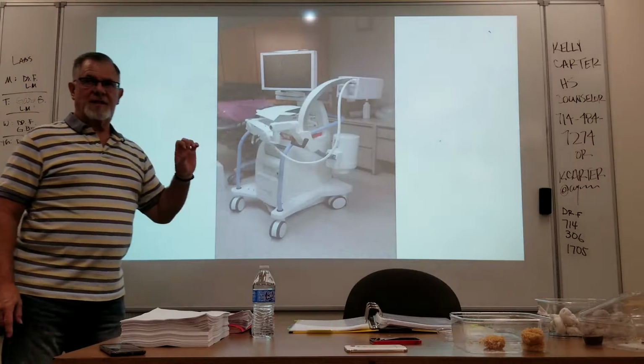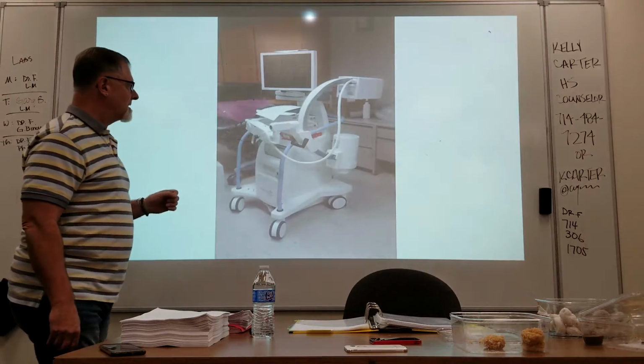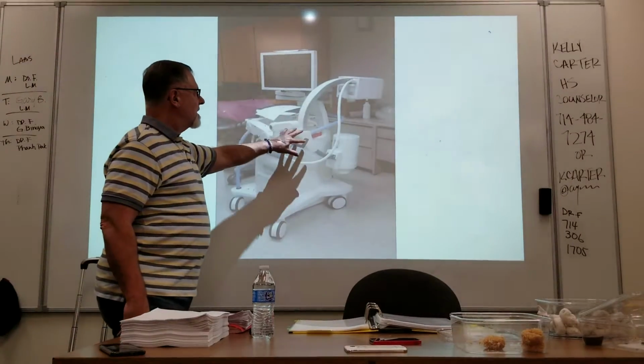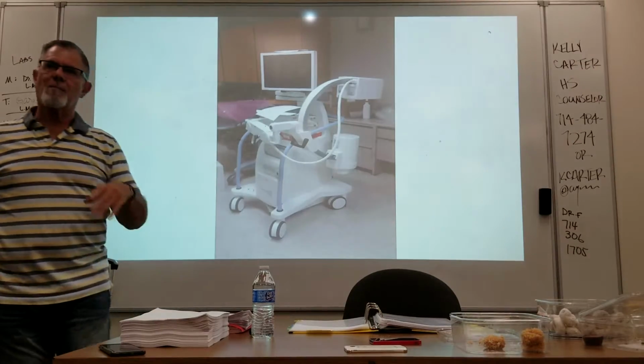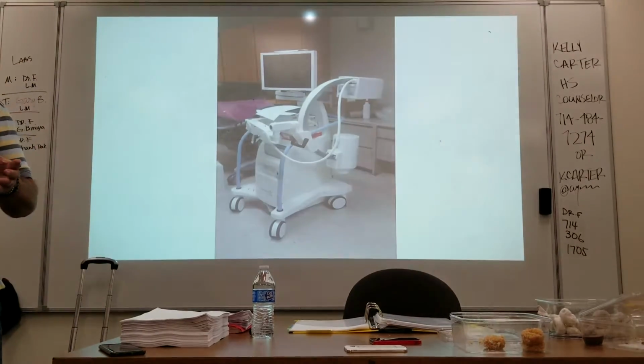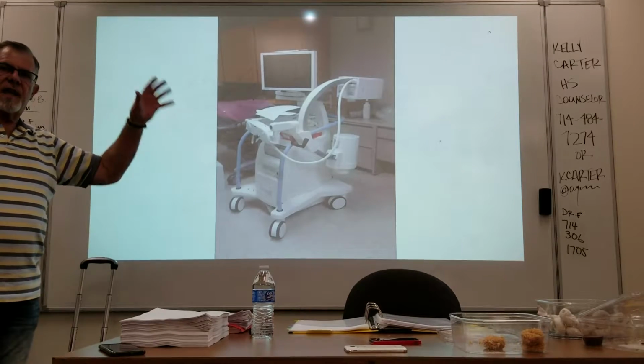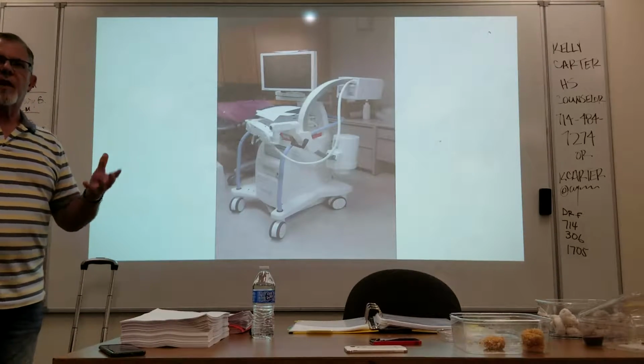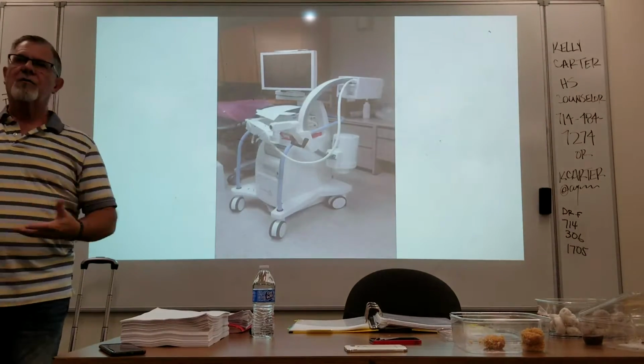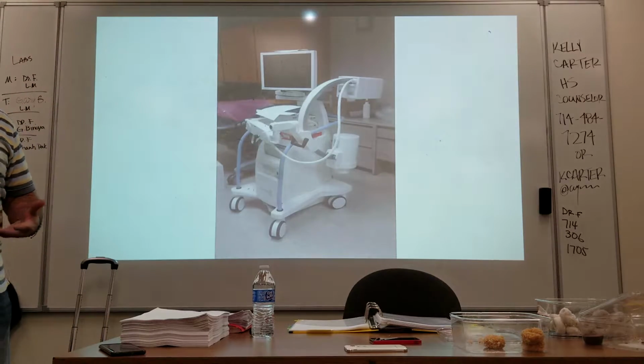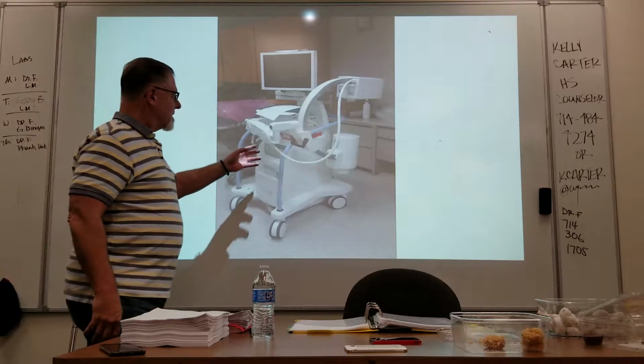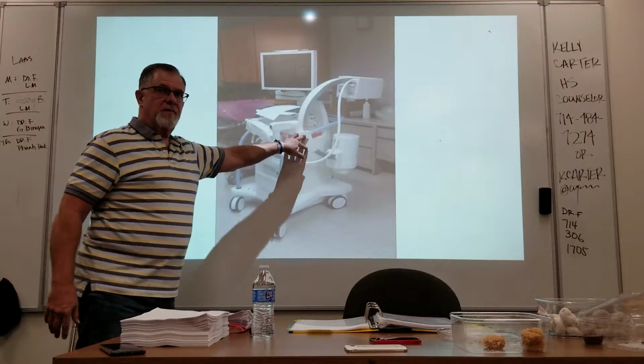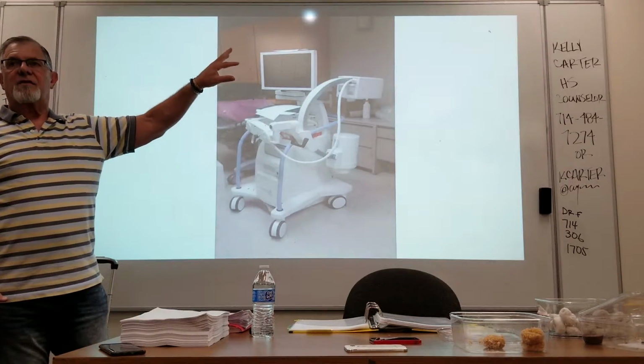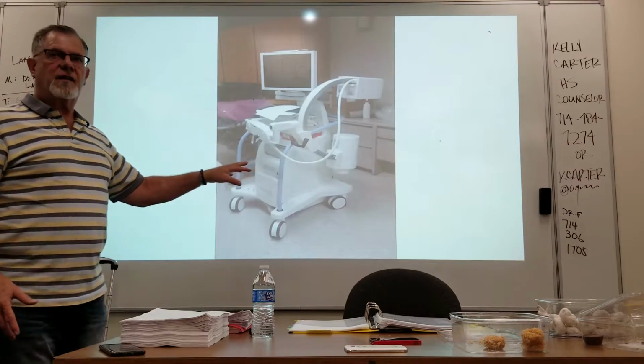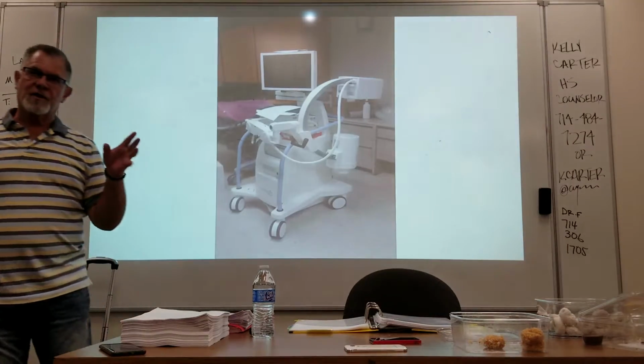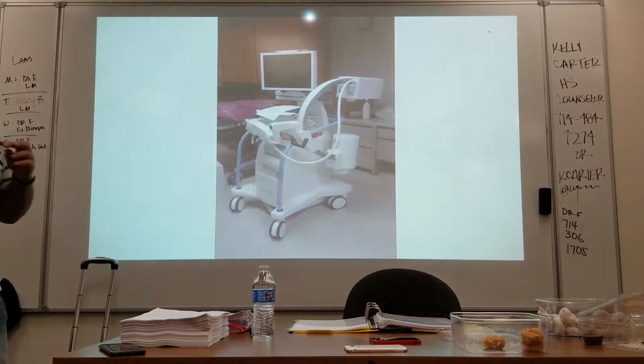Big problems with these. Number one, none of the pieces or parts of this are balanced very well. On the larger C-arms, everything is counterbalanced pretty well. If you undo a lock, it's not going to go flipping around. Nothing horrible is going to happen. If you flip a lock on some of these devices, things happen. Usually not good things, usually things that trap your finger or some other body part that you don't really want to get pinched.